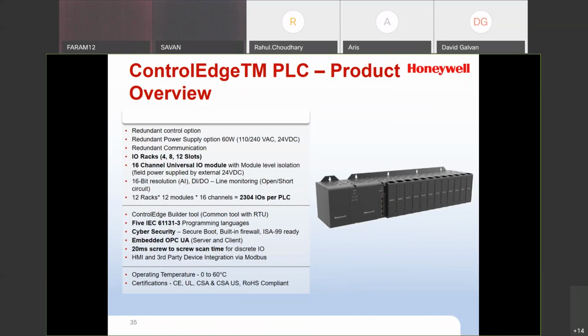If you're on ladder logic now and you want to say, you know what, the rest of the plant is function block, let's try to make our PLC networks function block also, we can do that. We can transition all of those ladders. If you have an obsolete PLC that needs to be replaced, we have transition tools that will transition your current ladder logic into either ControlEdge ladder logic or ControlEdge function block.